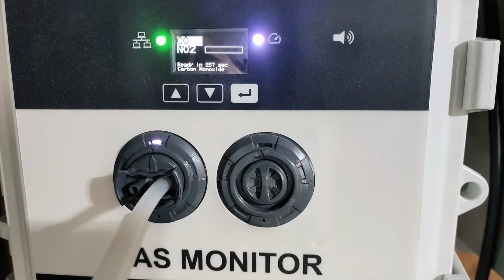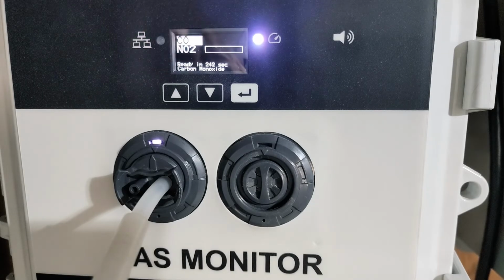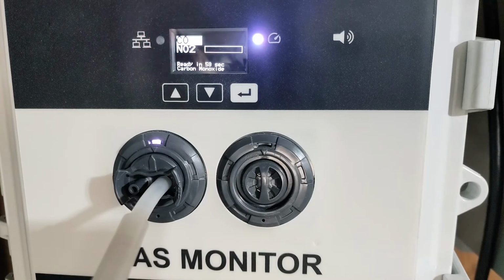It's important to note that the sensor module hardware is equipped to automatically hold its potential during a brief power outage, allowing for minimalized warm-up time. So in the event that the power goes out, the sensor module should be ready for gassing or concentration readings within 5 minutes. Once you're finished with calibrating, remember to remove your gas and turn off your calibration gas cylinder.